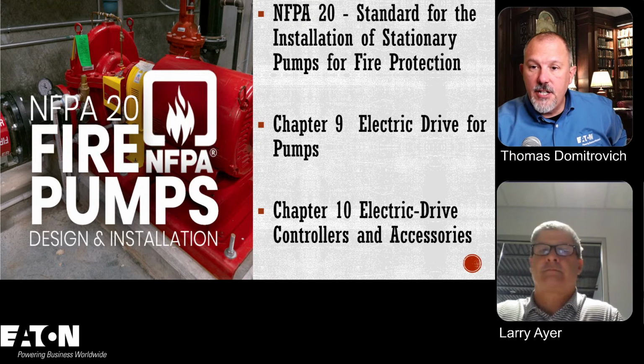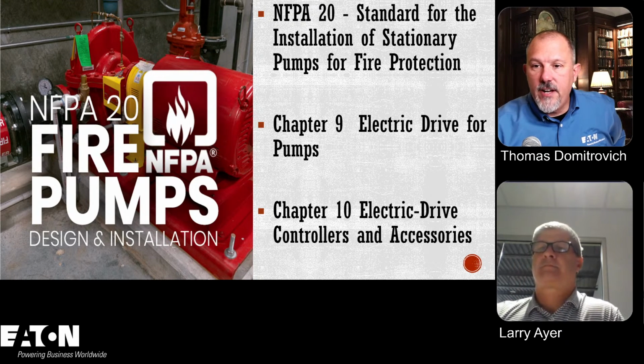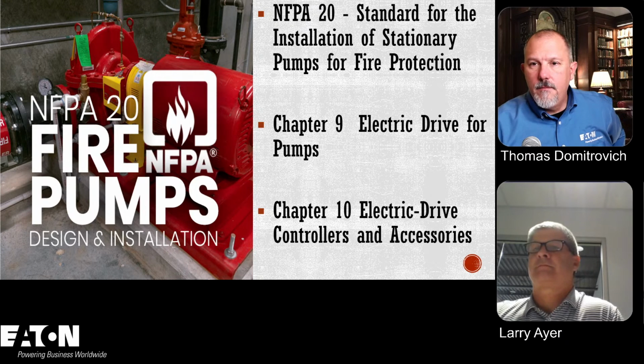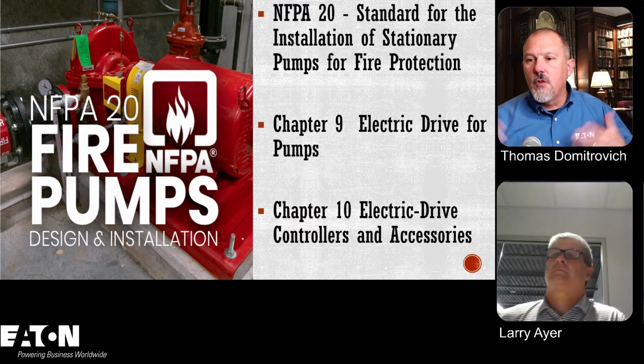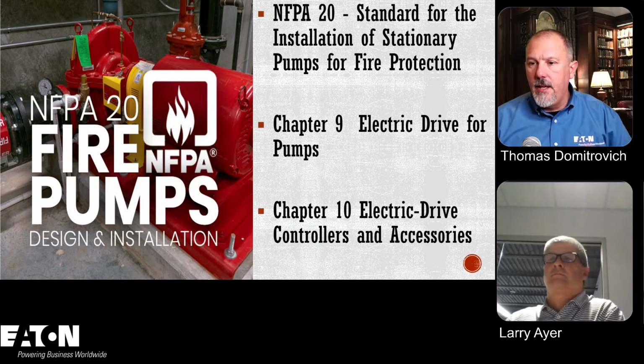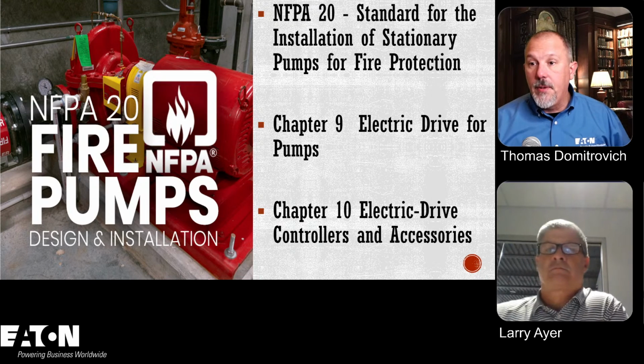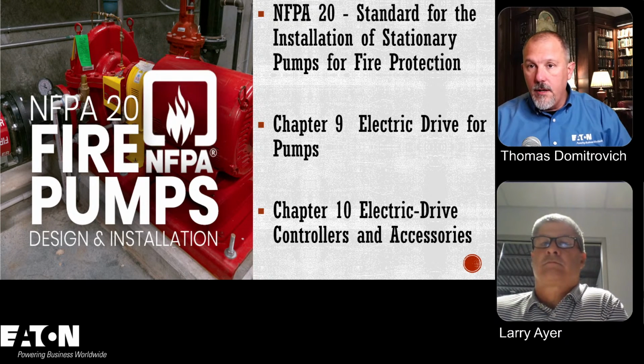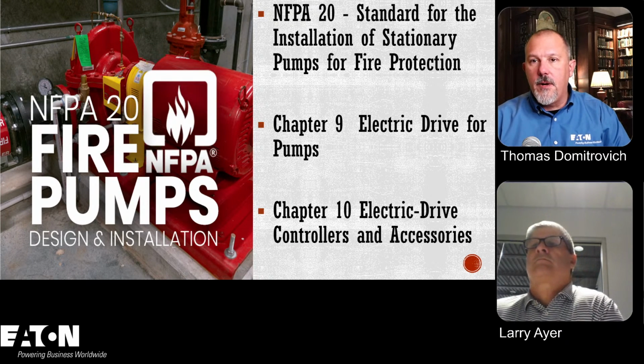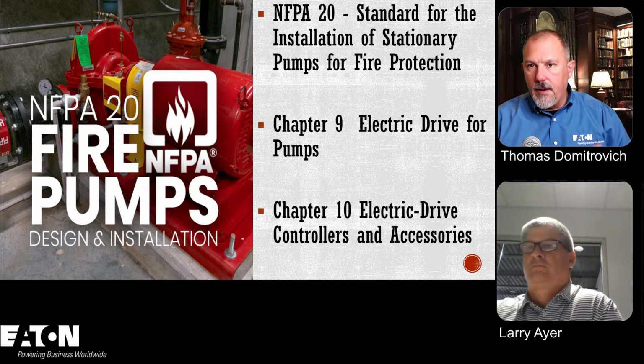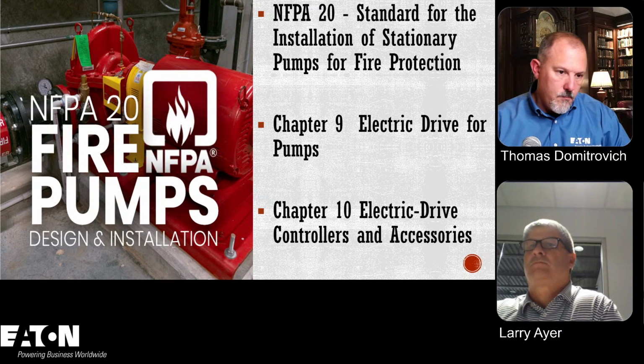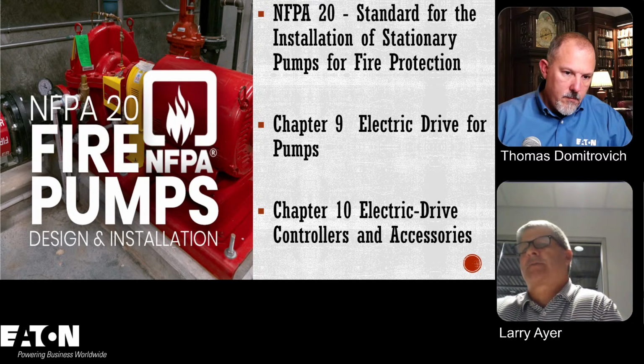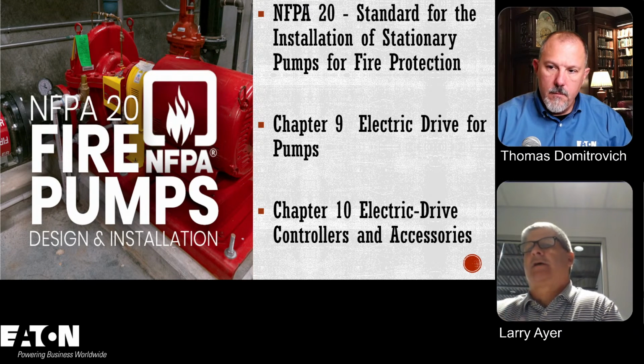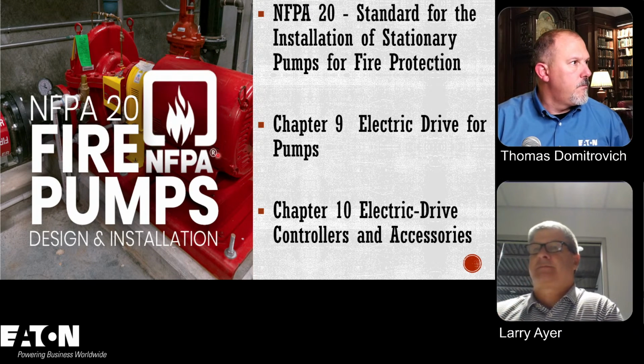Yeah, chapter 9 and chapter 10, electric drive for pumps and electric drive controllers. And I think in NFPA 20, you would have information about the water supply and all this other good stuff that, from an electrical perspective, we might not worry about, but from an overall design perspective and picking the pumps, if you're into fire pumps, you're probably going to be heavily ingrained in NFPA 20, I would assume. Yes, I would assume so, because I think chapter 10 gives you a little more detail on transfer switches and things of that nature. Excellent.